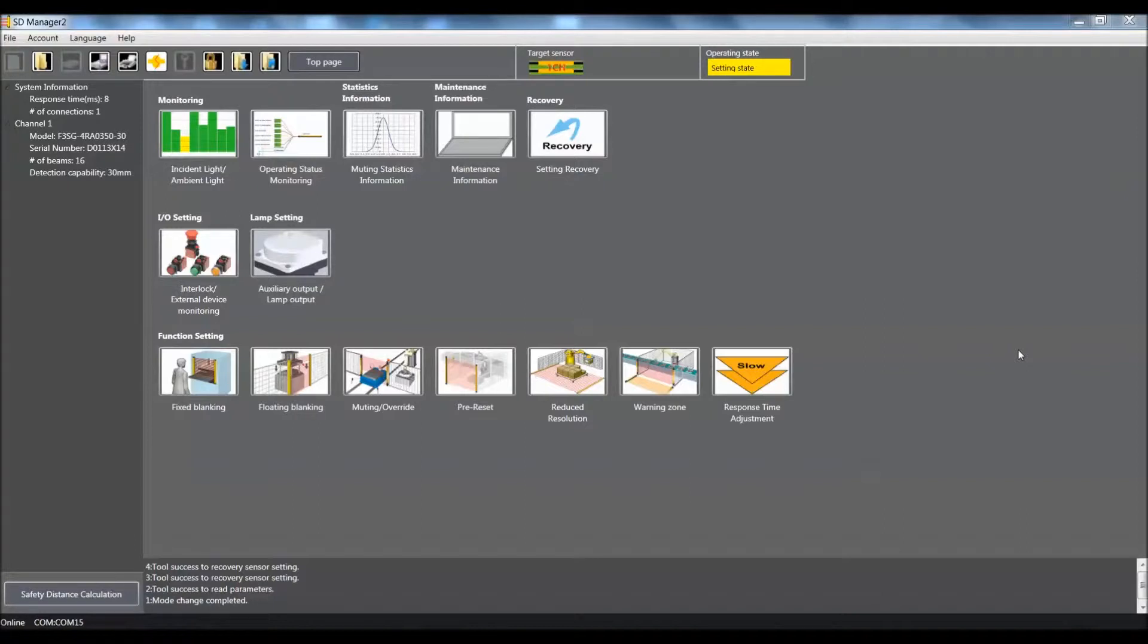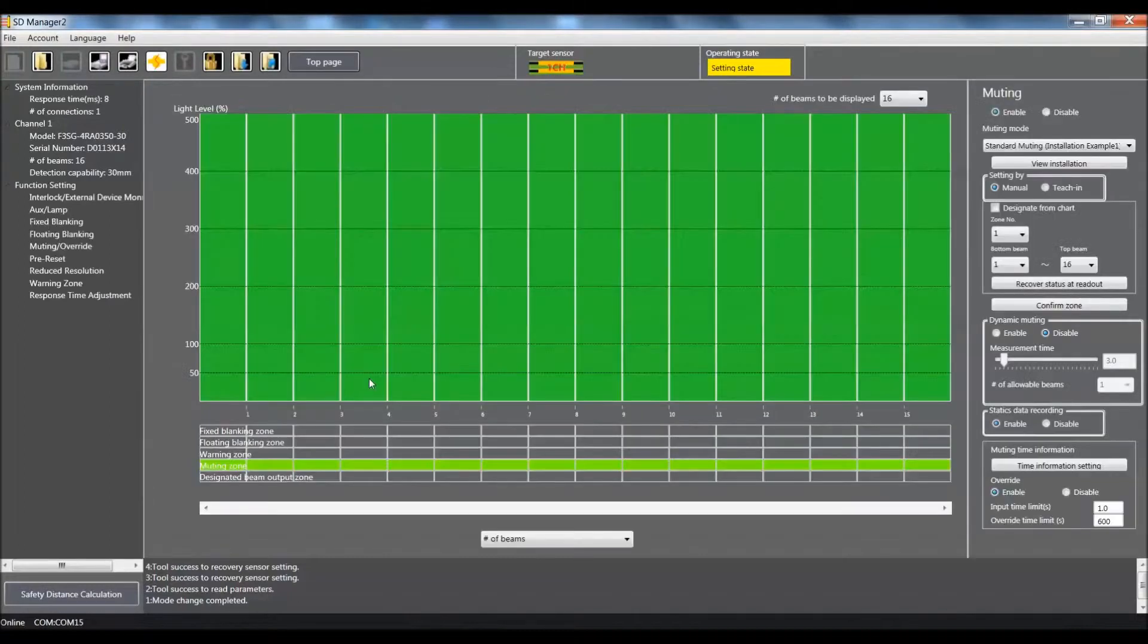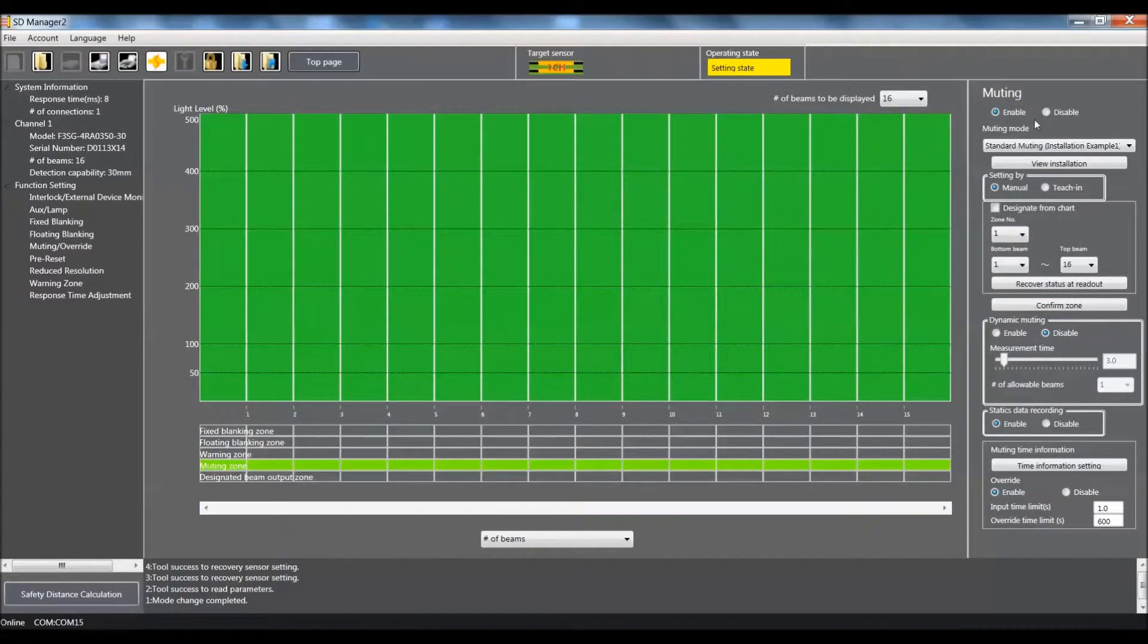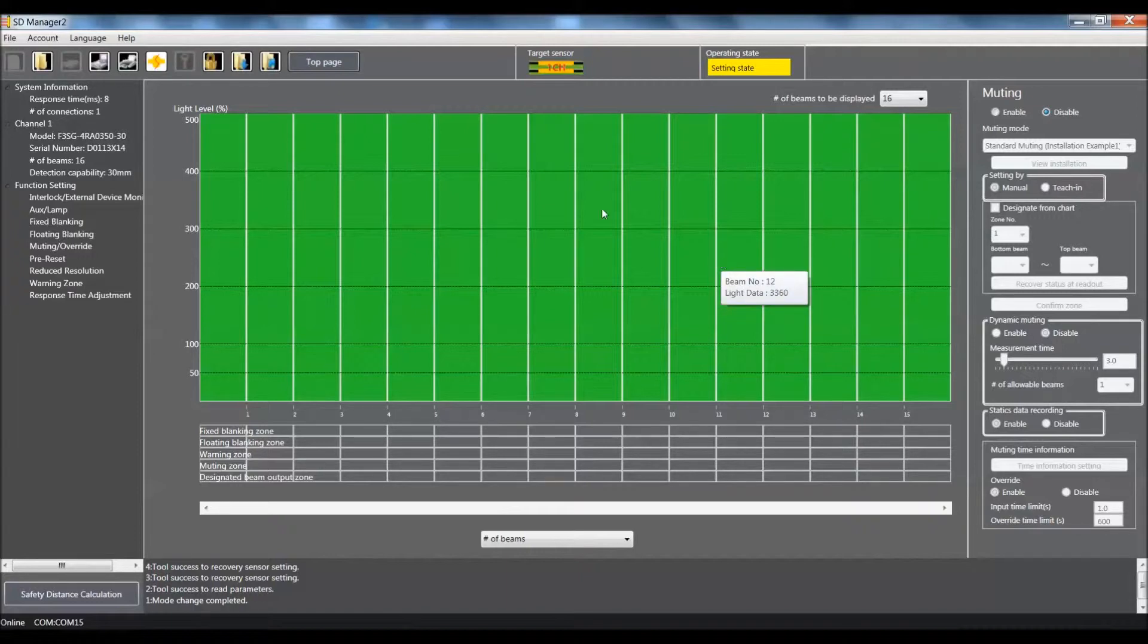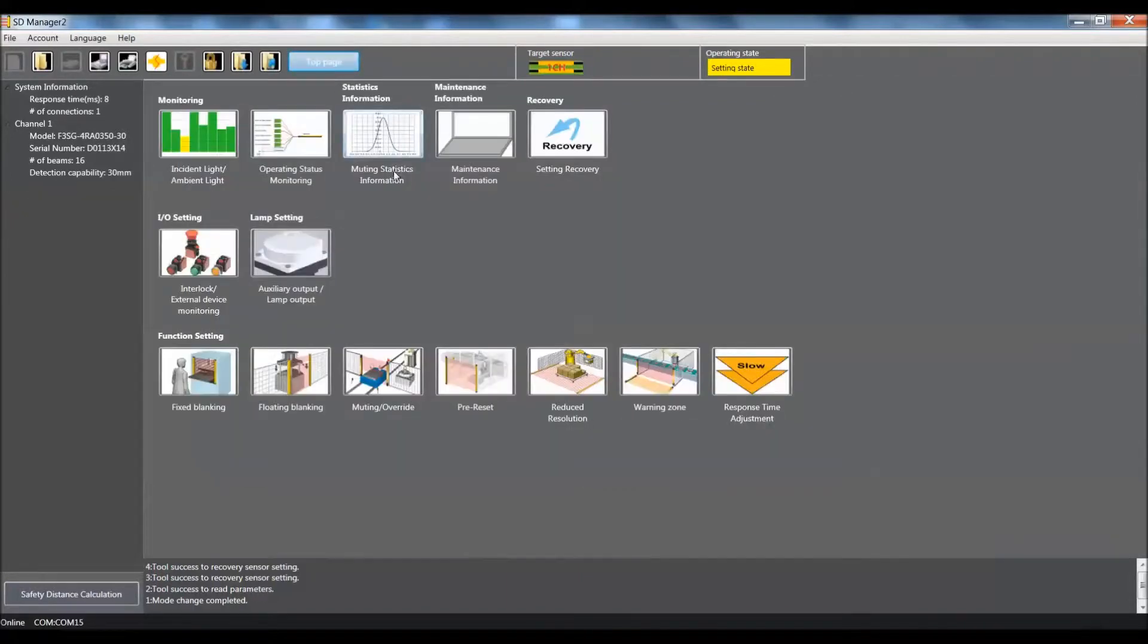Alright, first thing that we need to do is come into the muting override. The reason for this is we need to disable the muting function. You cannot use the muting function in conjunction with the reduced resolution feature in the F3SG.